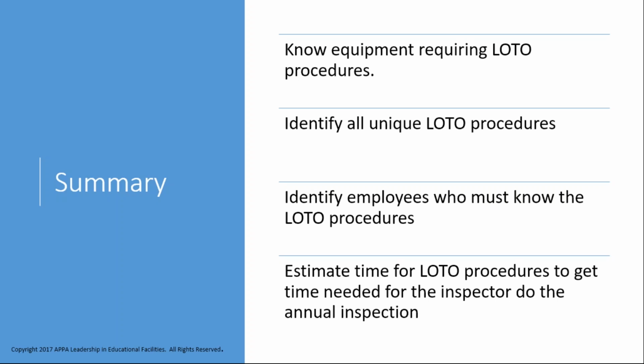Identify all unique lockout tagout procedures and identify the employees who must be familiar with the lockout tagout procedures to do their job safely. For instance, to maintain electrical equipment, you might have all electricians trained on lockout tagout procedures for all electrical equipment. It really depends on the kinds of assignments you give the electricians. However, for components such as a major air handler, it may be necessary to have electricians, plumbers, and HVAC technicians all trained on the lockout tagout procedures for the air handler, because each one of them has energy coming in from a source where they're responsible for the maintenance.